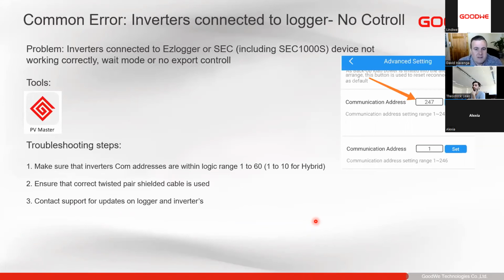So next is inverters connected to our loggers. So when we connect to your loggers, SC1000 or anything like that, to do power control, export power limit, or any of those other features, we need to make sure we set Modbus addresses on our inverters. Normally you'd see the inverter will also remain in a wait mode in many of these instances because they are waiting for commands from the logger. We just need to make sure to set the communication address correctly on the inverters.